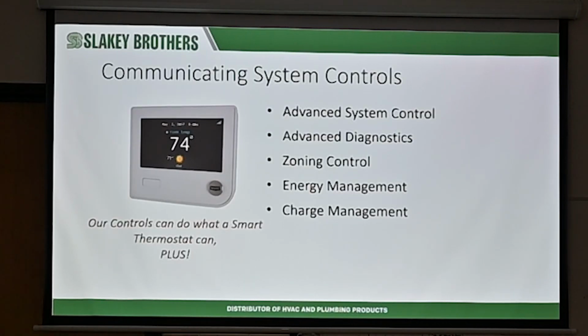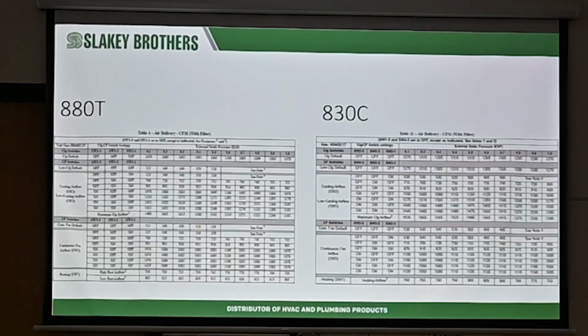If I have a Connex and a high-end system furnace, if I adjusted dip switches, will my Connex override these dip switches? Yeah. So even though you've got dip switches on it, you can flip dip switches trying to get the CFM, it's not going to do anything. The nice thing about the Connex being a communication system overall is you're telling it what the outdoor unit's tonnage is. Because for instance, you can do a 5-ton furnace and put a 3-ton air conditioning unit on there. Once the system communicates and notices that, it's going to know it needs to dumb itself down and slow down. We're not going to do 2000 CFM. We're going to do 1200 or 1050 if it's 350 CFM per ton. It will automatically do all that for you. If you take the Connex out of there, do the dip switches.